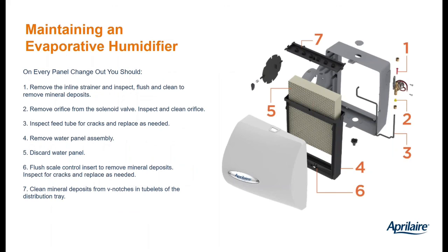We offer maintenance kits. It's the easiest way to maintain the humidifier. I'm a big fan of if it ain't broke, don't fix it. I did tech support for a lot of years, and I've seen guys take apart the solenoid valve, lose the orifice, then they've got way too much water going through the unit. I've seen guys try and clean out the orifice, end up reaming it out, and they get way too much water going through it. That orifice has a tiny, tiny hole. Depending on what color orifice it is, it's like a number 73 or number 77 drill bit. It's a tiny, tiny hole.